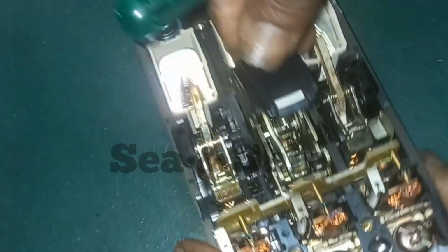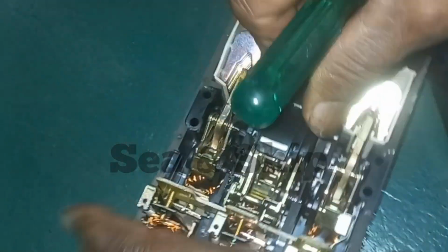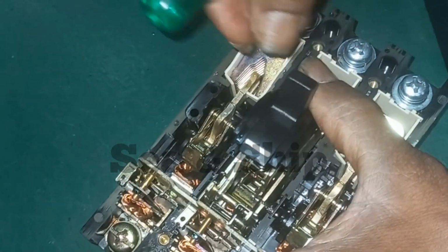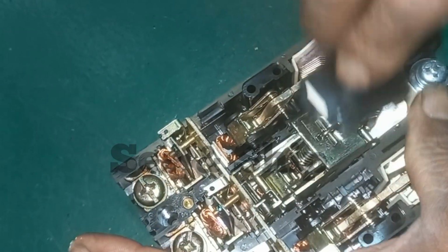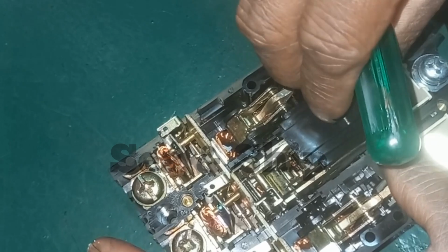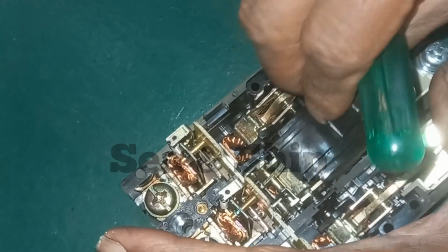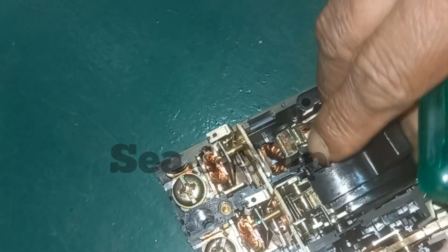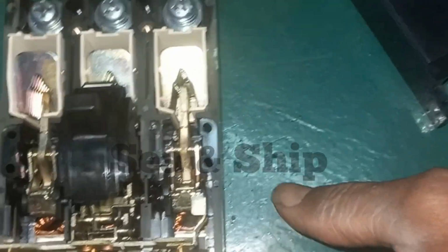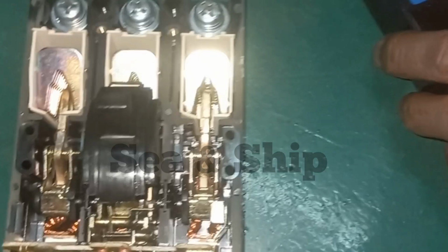It is used for main switchboards, generators, and large motors. It has a much higher breaking capacity, meaning it can safely break a huge short-circuit current without exploding. And because of adjustable settings, we get proper selectivity. That means if one pump has a fault, only that MCCB will trip, and the whole ship won't go blackout.